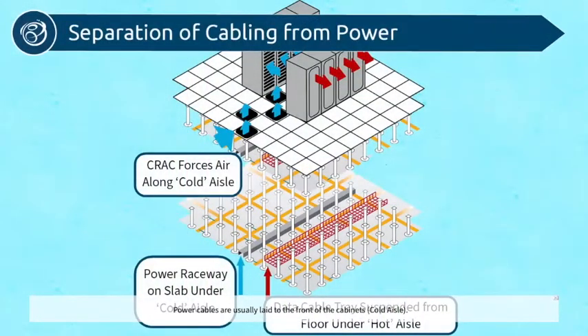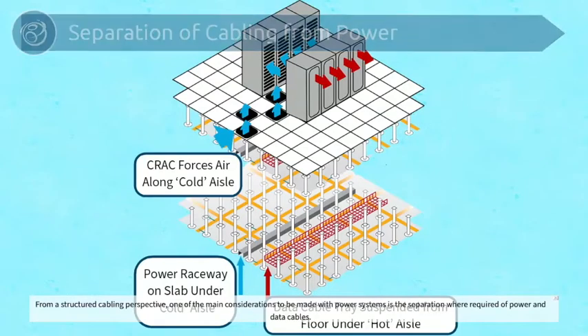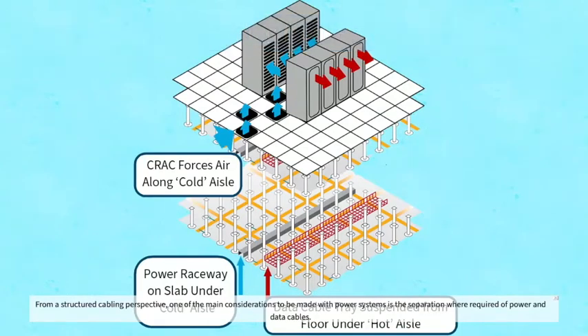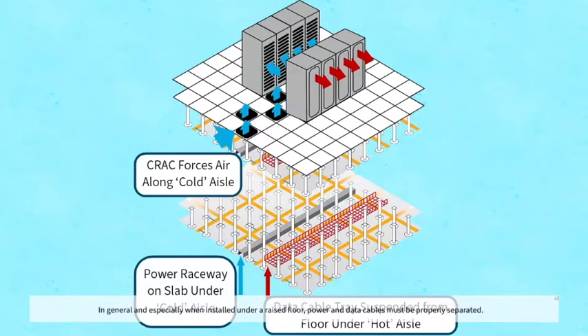Power cables are usually laid to the front of the cabinet's cold aisle. From a structured cabling perspective, one of the main considerations to be made with power systems is the separation, where required, of power and data cables. In general, and especially when installed under a raised floor, power and data cables must be properly separated.